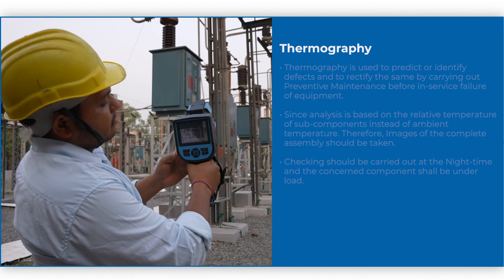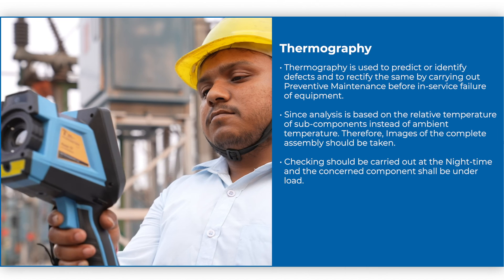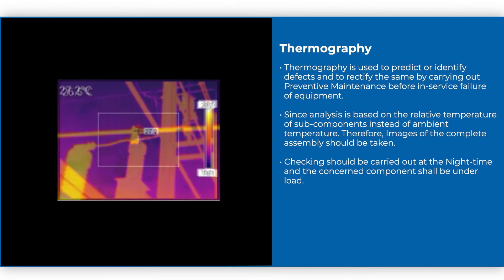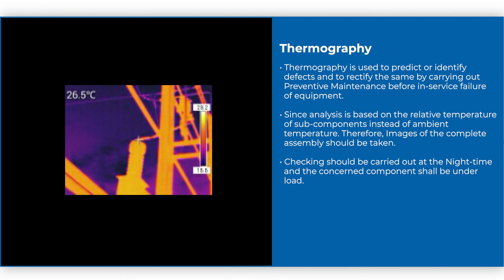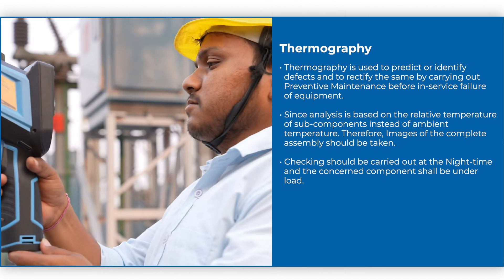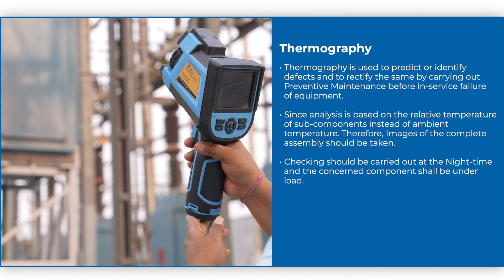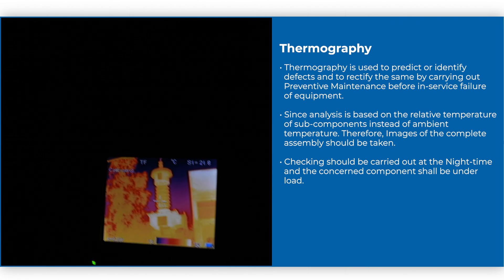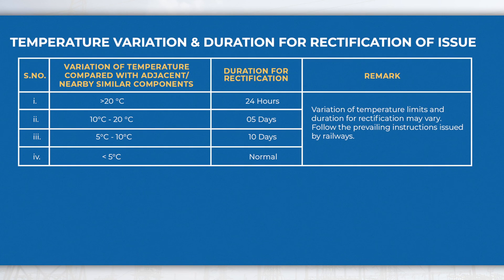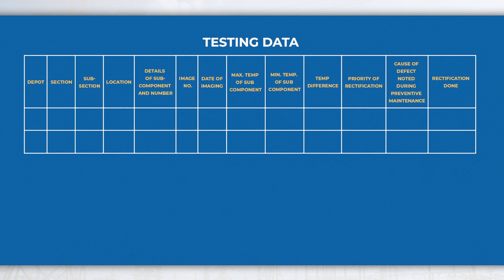Thermography: Thermography is used to predict or identify defects and to rectify them by carrying out preventive maintenance before in-service failure of equipment. Since analysis is based on the relative temperature of subcomponents instead of ambient temperature, images of the complete assembly should be taken. Checking should be carried out at night time and the concerned component shall be under load. The limit for temperature variation and duration for rectification of issues is given in the table. Testing data may be recorded in this format for further investigation and future reference.